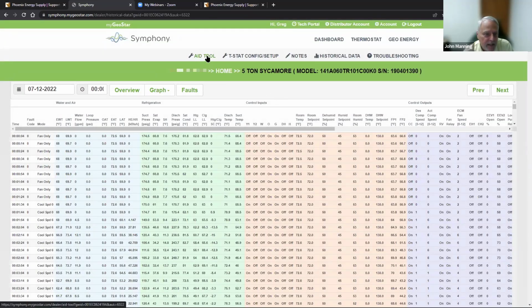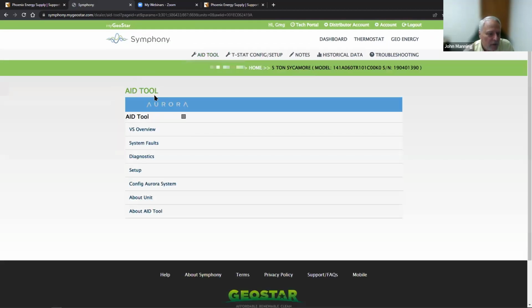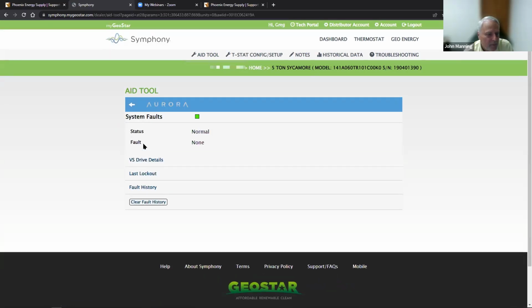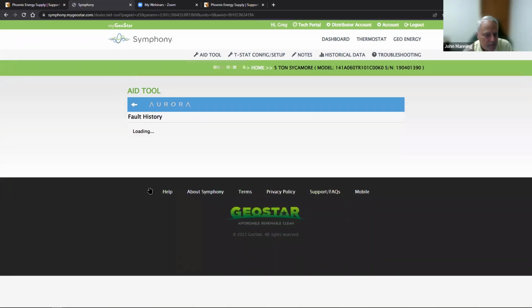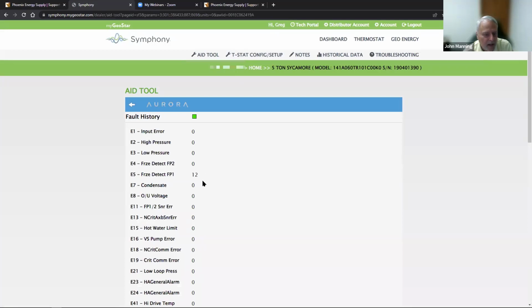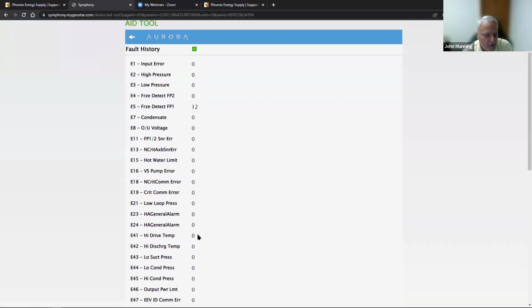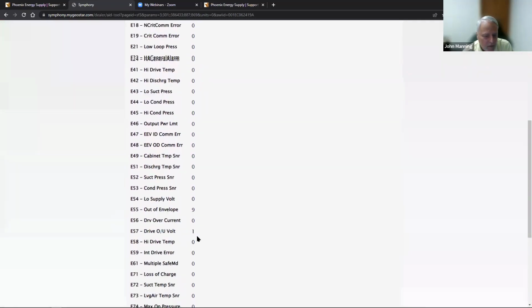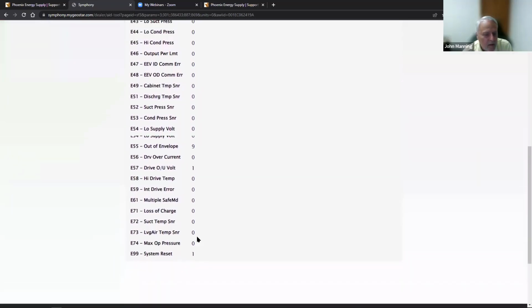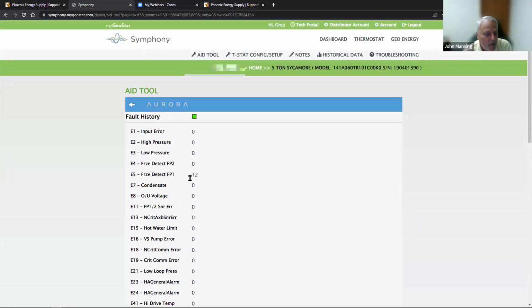You can access the aid tool remotely. You can, under diagnostics or system faults is a good one. We can look at the fault history. And it tells us how many times the unit tripped on a particular fault, and there's a lot of them that it keeps track of. Quite often the FP1 fault, which is freeze protection, you might get a few of those on startup when you're debugging the system. Another chart that I like is the geo energy.